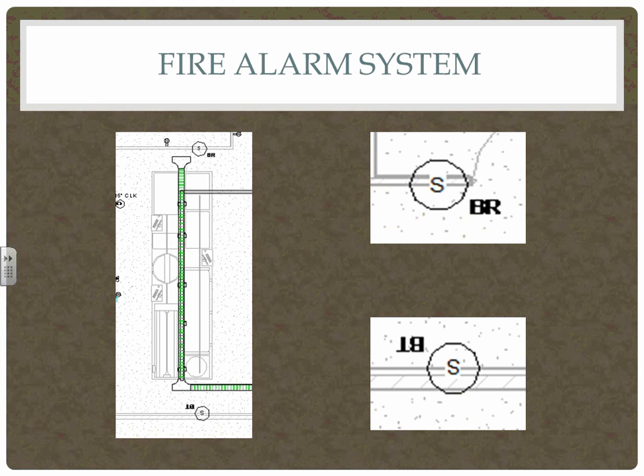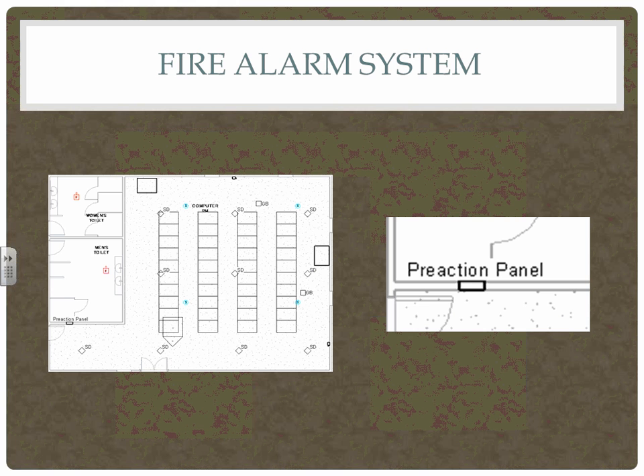On the manufacturing floor for the fire alarm system, we had a beam smoke detector. We had the receiver and the transmitter, and it would just send a signal across. If smoke got up to that level, then the fire alarm would go off. We thought this was the best way to protect the roof with such a big space. This is the data center, and in here we have a pre-action fire alarm system, which I think was similar to the one at Allianz. The only way we would dump chemicals or liquids onto all this equipment was if we were 100% sure that there was a fire, and not just some clumsy maintenance guy knocking something over. We just want to make sure the alarm didn't go off by accident.